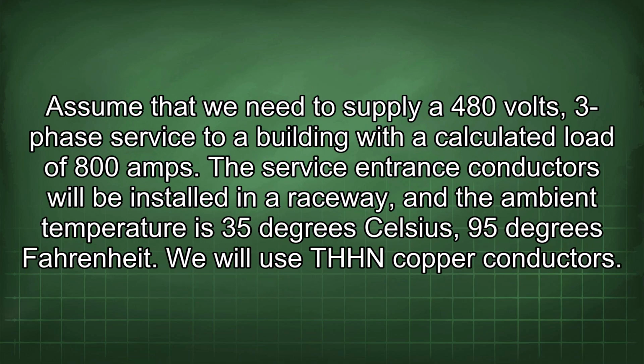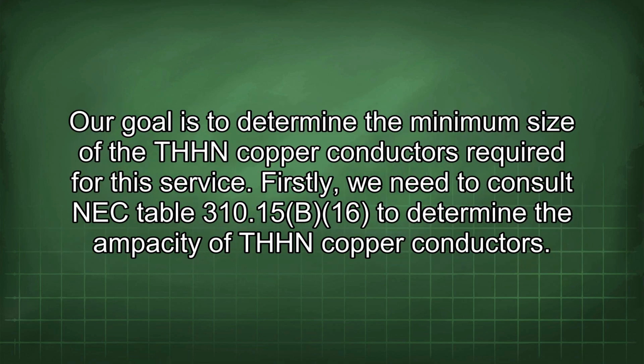Assume that we need to supply a 480 volts, three-phase service to a building with a calculated load of 800 amps. The service entrance conductors will be installed in a raceway, and the ambient temperature is 35 degrees Celsius, 95 degrees Fahrenheit. We will use THHN copper conductors. Our goal is to determine the minimum size of the THHN copper conductors required for this service.